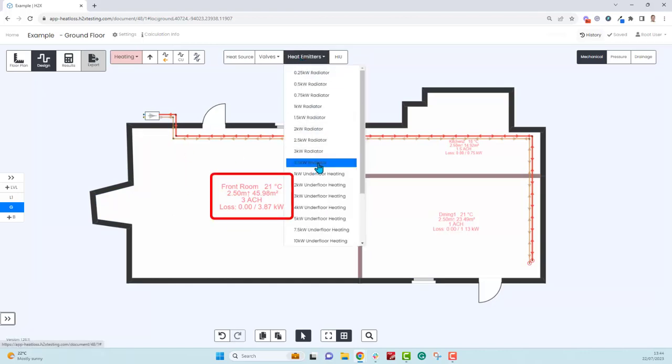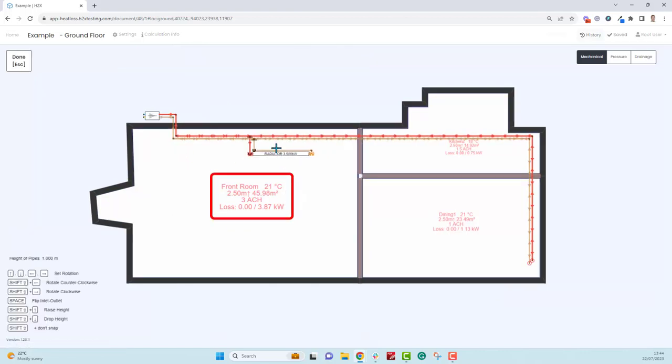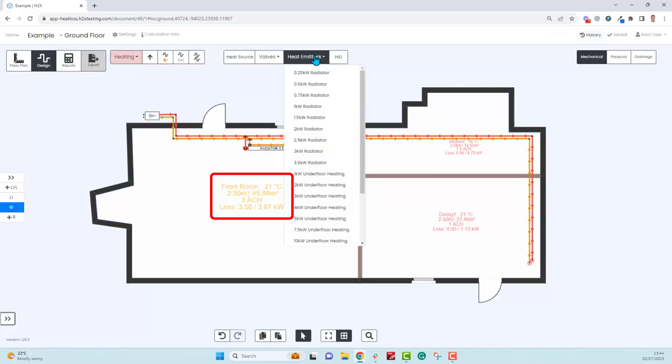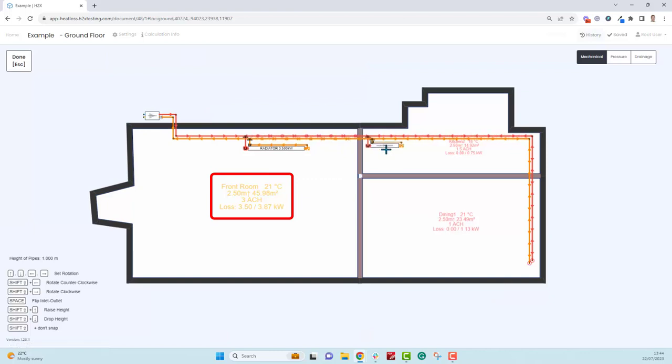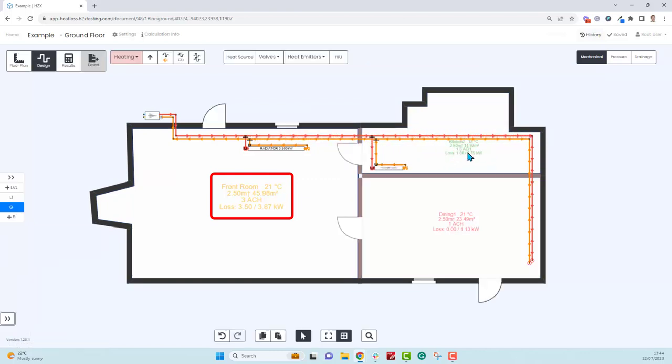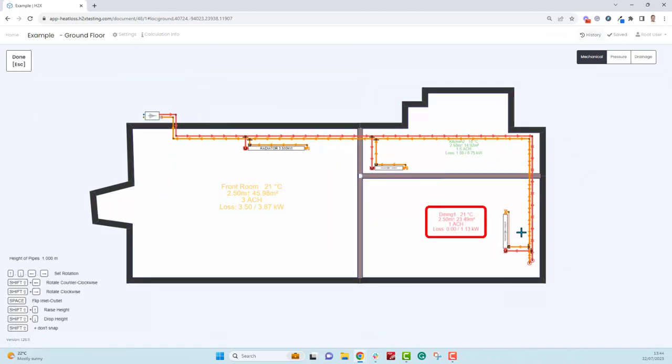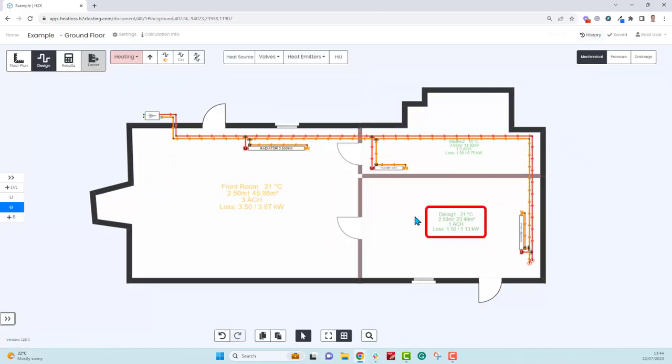You'll notice the text in the rooms is red and that's because we haven't provided heat emitters with enough kilowatt load to meet the heat loss. So there we have 3.87 in the front room and only 3.5 kilowatt heat emitter so it doesn't quite turn green. Whereas in the remaining two rooms, as we add heat emitters that exceed the heat loss, you can see the text does turn green.